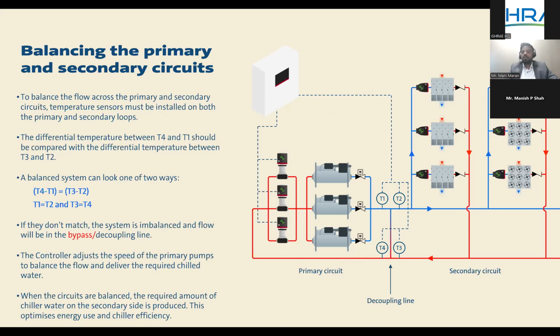So it's pretty simple. If your secondary flow is more, it impacts your temperature across the decoupler, and that feedback is given to the controller to increase or decrease the speed. That's how we balance the system.